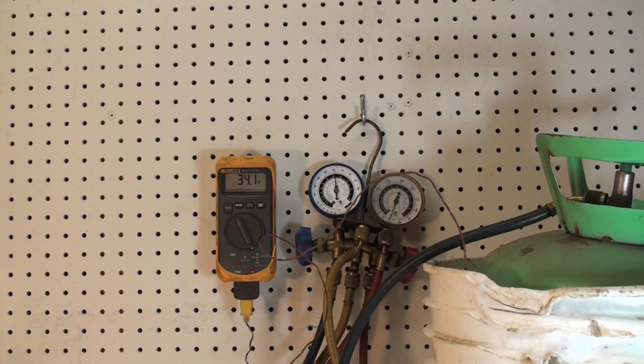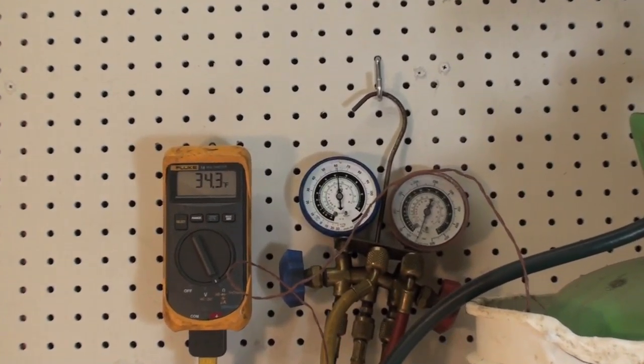Now I'm going to change the temperature of that cylinder and let's see what happens. Okay, now what I've done, you can see over there in the right I've got the cylinder placed in a bucket. Now that bucket's got ice water in it and so that's going to lower the saturated temperature pressure of the liquid and gas mixture that's in it. Well, let's see what our gauge says.